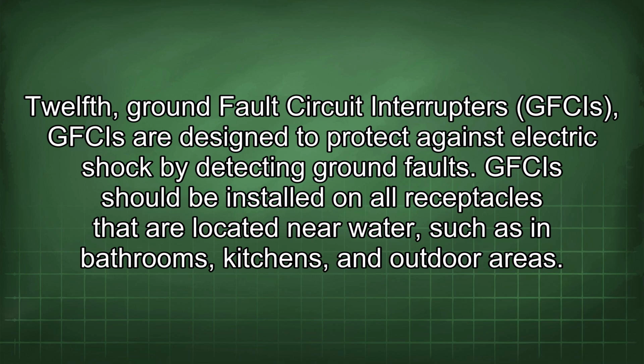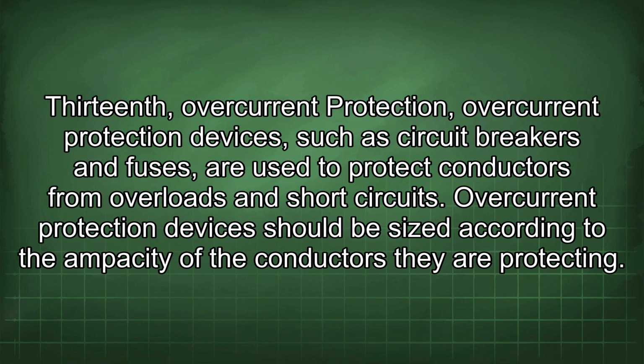12th, ground fault circuit interrupters (GFCIs). GFCIs are designed to protect against electric shock by detecting ground faults. GFCIs should be installed on all receptacles that are located near water, such as in bathrooms, kitchens, and outdoor areas. 13th, overcurrent protection. Overcurrent protection devices, such as circuit breakers and fuses, are used to protect conductors from overloads and short circuits. Overcurrent protection devices should be sized according to the ampacity of the conductors they are protecting.